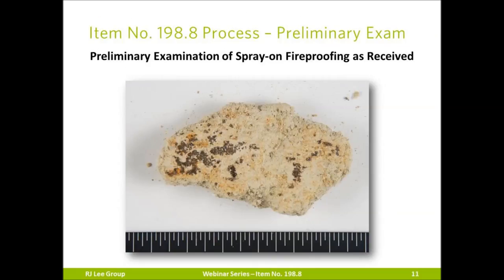Preliminary examination of the as-received fireproofing begins with a binocular microscope examination to check for the presence of layers or lack of homogeneity. If layers are observed, then each layer is treated as a separate sample. The material is then checked for the presence of vermiculite. Finally, the sample is checked for the presence of asbestos bundles.